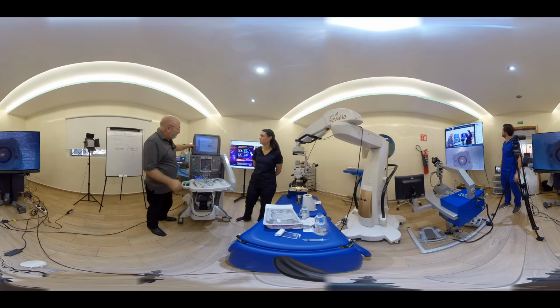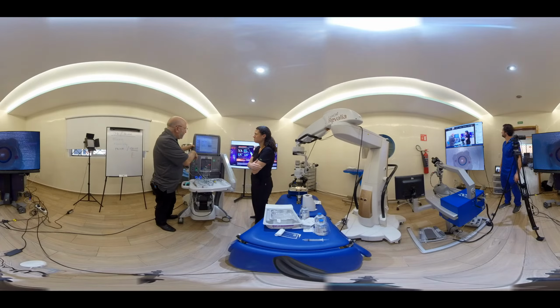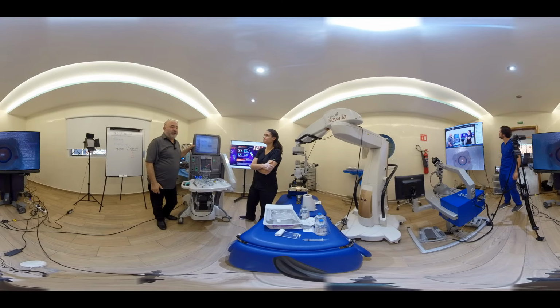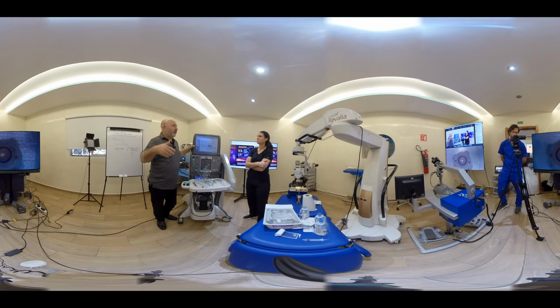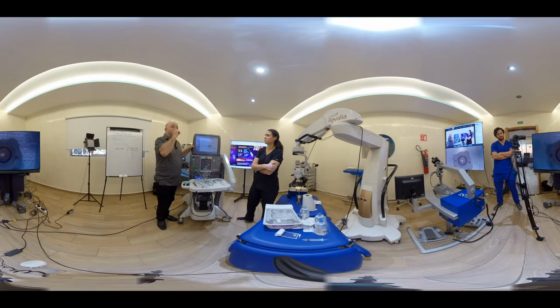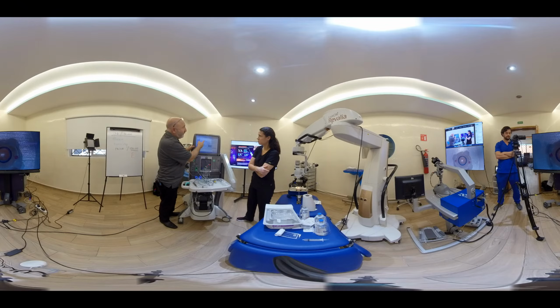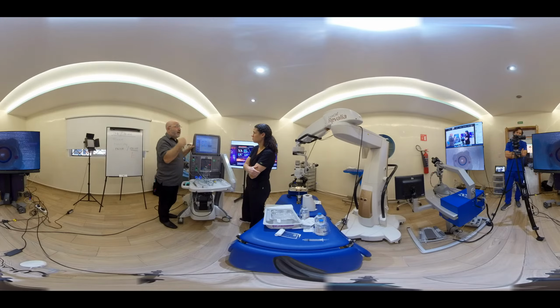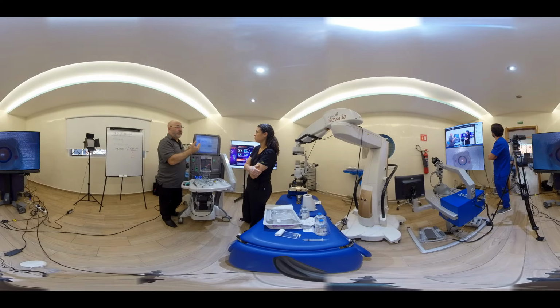Just while we're on this page, I was with another surgeon earlier in the week who was annoyed at the pinging when you're in elevated infusion pressure. So you get this warning, ping, ping, if you go to 60, and you get the lady saying, you're at 60, pressure, whatever, and it's got the time. Well, that is set by you. It's default, and here it is. 51 is the threshold. So you're telling me here, elevated infusion threshold, I want you to start warning me when anything from 51 and above. But you can change that to be anywhere you want.